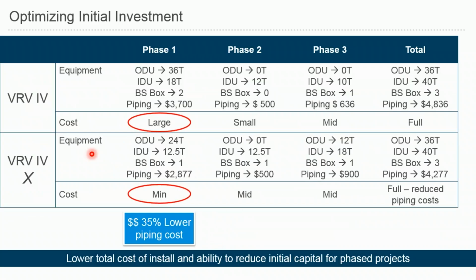So overall, when you look at the difference between VRV4 and VRV4X in this example, you saw that with VRV4 you had to install the largest capacity unit, 36 ton with triple module configuration, and to get to the minimum connection ratio, you had to install about 18 ton of indoor units with 2 branch selector boxes. And your piping cost was higher as well because you were using larger main pipeline sizes in that case.